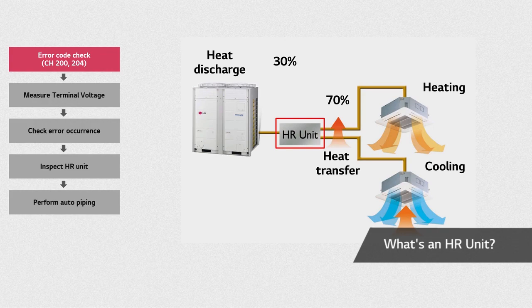Once the HR unit gets the signal from the outdoor unit, it starts communicating with indoor units and then performs pipe detection. Errors CH200 and CH204 can occur at any of these steps.